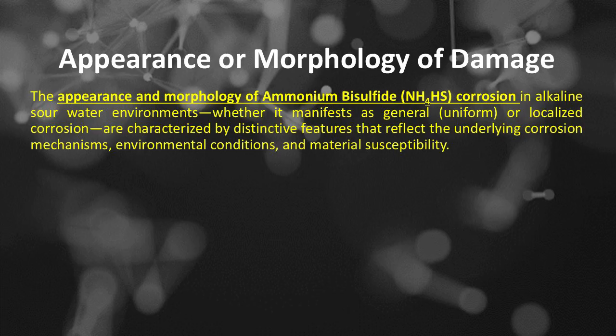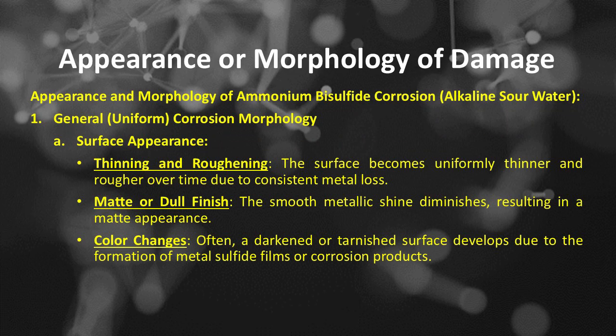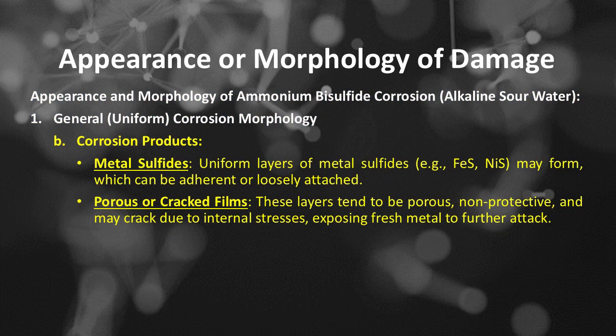The appearance and morphology of ammonium bisulfide, NH4HS, corrosion in alkaline sour water environments, whether it manifests as general, uniform, or localized corrosion, are characterized by distinctive features that reflect the underlying corrosion mechanisms, environmental conditions, and material susceptibility. Number 1 is general or uniform corrosion morphology. The surface appearance includes thinning and roughening: the surface becomes uniformly thinner and rougher over time due to consistent metal loss. Matte or dull finish: the smooth metallic shine diminishes, resulting in a matte appearance. Color changes: often a darkened or tarnished surface develops due to the formation of metal sulfide films or corrosion products. Corrosion products of general or uniform corrosion include metal sulfides.